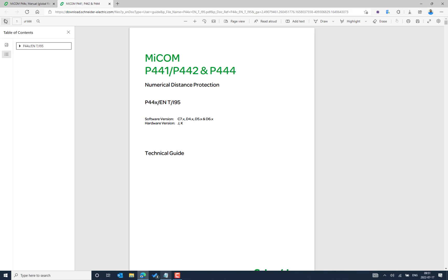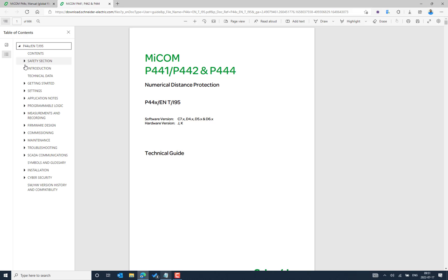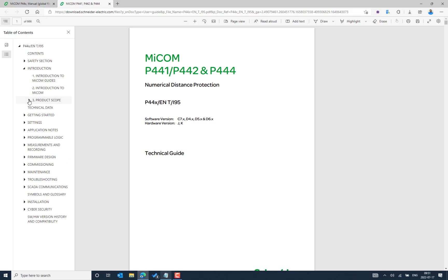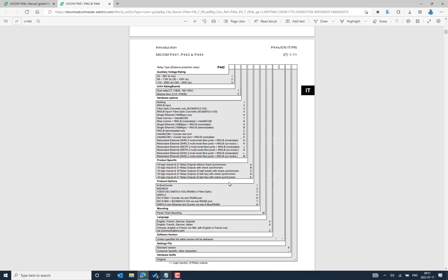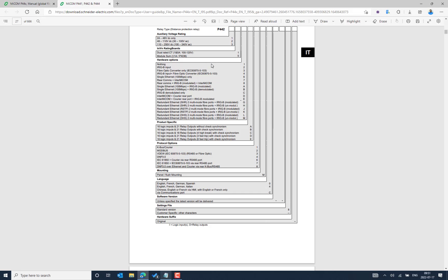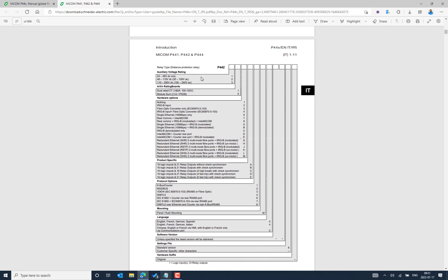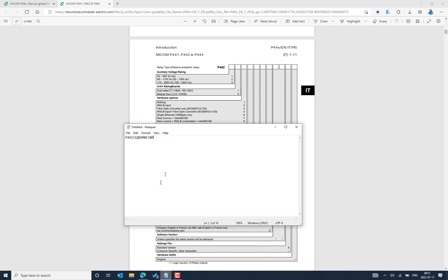Let's expand the table of contents and go to the introduction, product scope. There we can find the order option. This is for the P442, and here we can understand the different order options. For example, P stands for protection and 4 stands for the type of application — it's a distance protection relay.